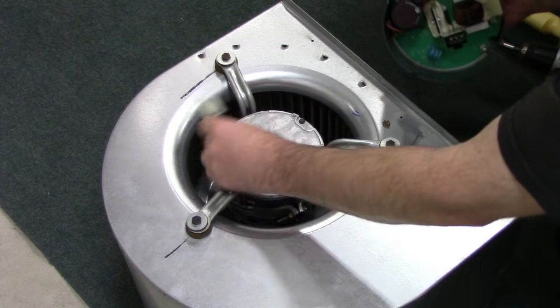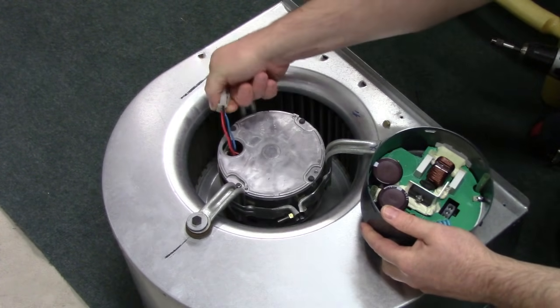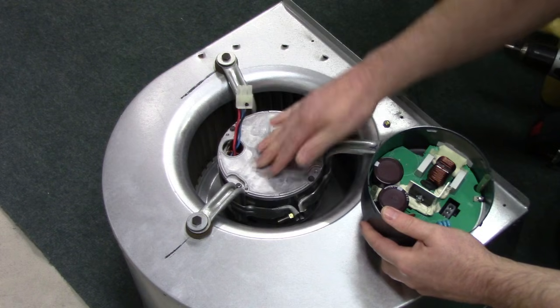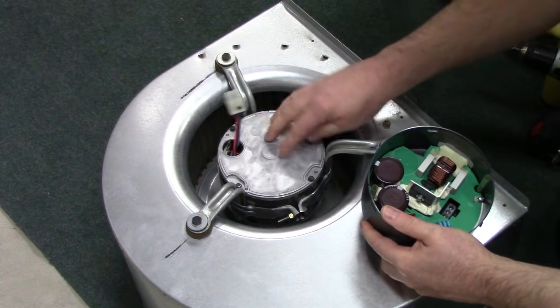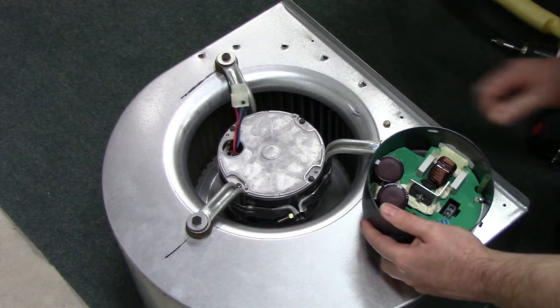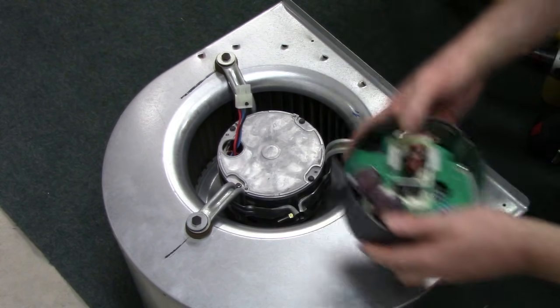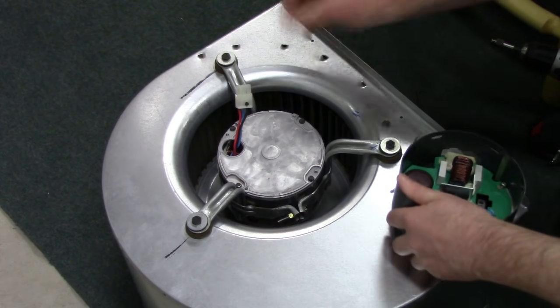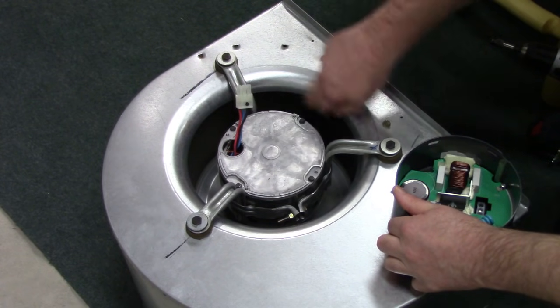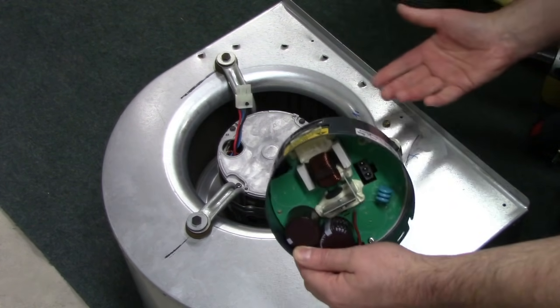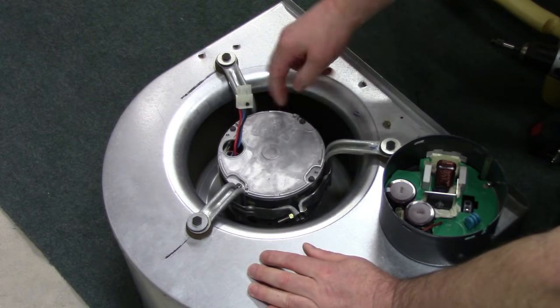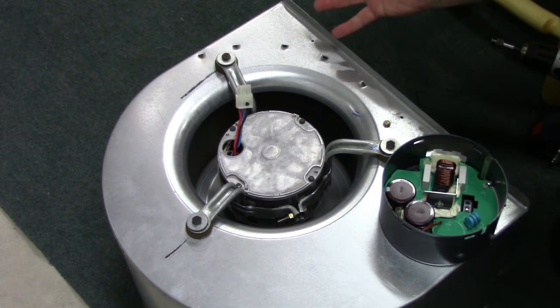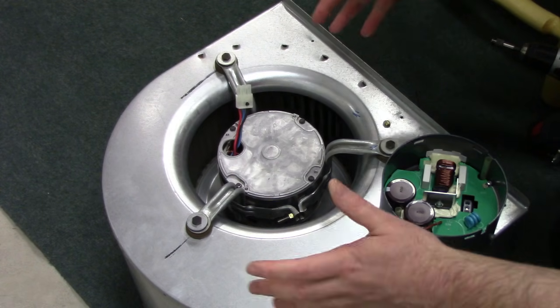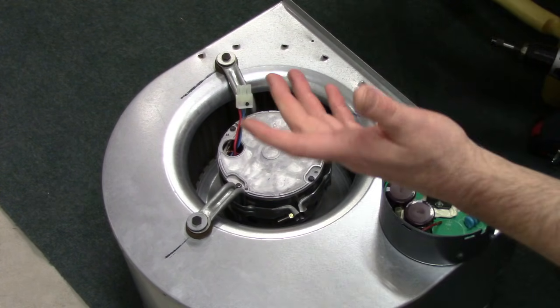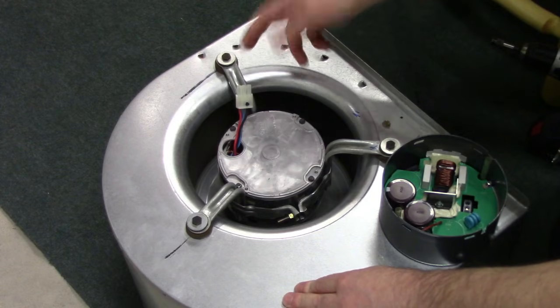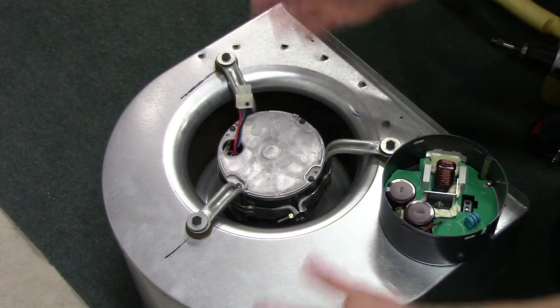There we go. So again, 3-phase DC motor. There's our 3 wires, like many of us RC people are familiar with on our brushless 3-phase DC motors. So before you can condemn anything, the first check is to see if the motor is actually turning. You could do that even before removing the ECM module, of course. But as long as the motor is turning smoothly, you know the motor's not jammed. Error code 41 means the computer in the furnace is not seeing that the motor is turning. So it's turning fine.